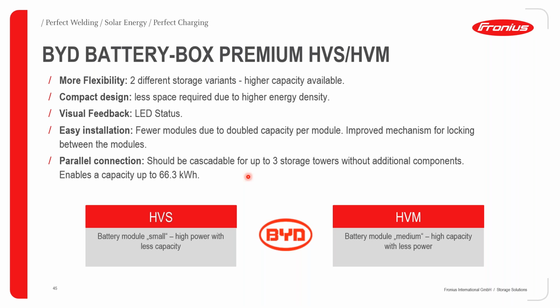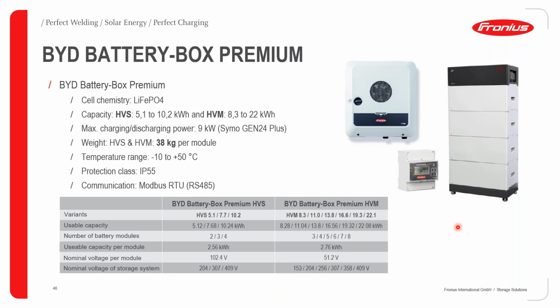There is already a document available to show you the compatibility for parallel connection between the BYD and the Fronius Gen 24 inverters. So when you are considering the design of this kind of system, always be sure to check the compatibility or the recommended configuration between BYD and the Fronius Gen 24 inverter. To give you more specific details, these batteries, of course, can also be installed outdoors. You can see here that the IP protection class is quite high, IP55. And the communication between the Gen 24 and the BYD Battery Box happens through the Modbus RTU channel.